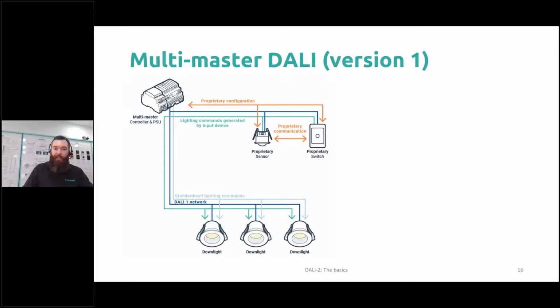So what actually had to happen is that we had these proprietary commands, often things like DALI or other little modifications on the base protocol, and they were sending little pings between them. The first sensor would say, okay, I've still detected someone here, and let that other sensor know that there's still someone in that room. So don't turn the lights off just yet. Look, I'm still seeing someone. And these two devices had to start talking to each other to ensure that the lights were only turned off when that room was vacated.